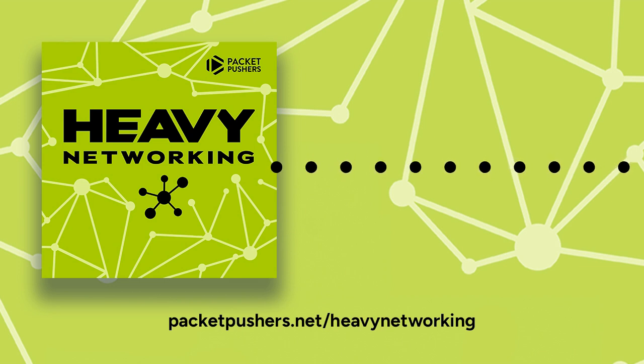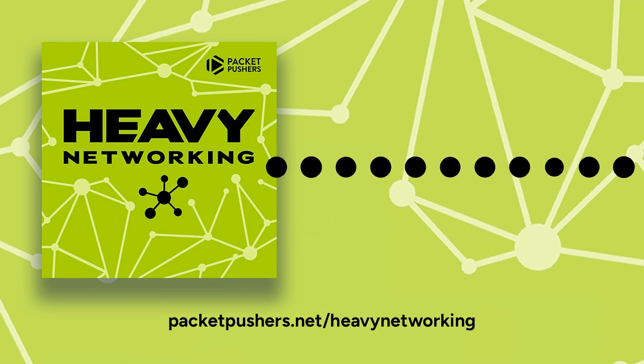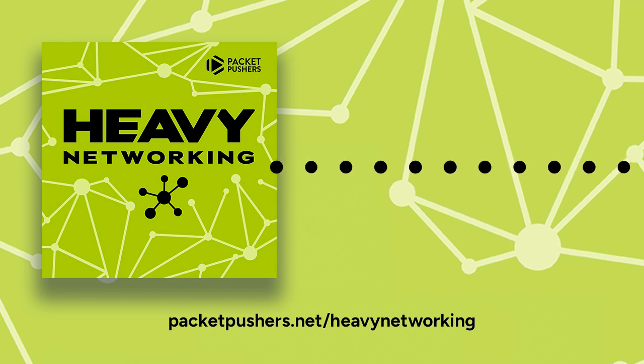Do they have a BACnet spec that's Ethernet only, or is it IP as well? It's IP. But they sent out a spec that uses, I believe, UDP with its own port number - it's its own thing. They actually have a way for BACnet IP devices on different subnets to talk to each other, using a BACnet broadcast management device, a BBMD, that sits on the subnet.